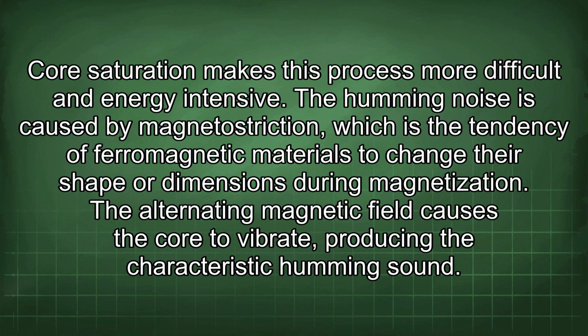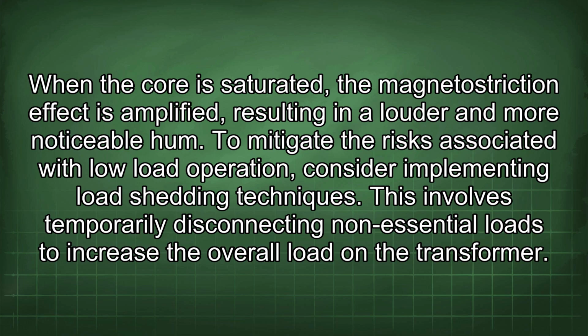The humming noise is caused by magnetostriction, which is the tendency of ferromagnetic materials to change their shape or dimensions during magnetization. The alternating magnetic field causes the core to vibrate, producing the characteristic humming sound. When the core is saturated, the magnetostriction effect is amplified, resulting in a louder and more noticeable hum.